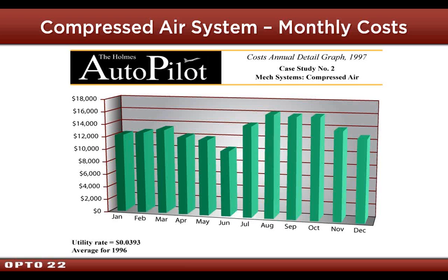He said, "By changing the way we were controlling our compressors, we've knocked 25% off of our daily and weekly consumption and cost, and it's going to save us $250,000 this year." This was a GE plant spending $1 million a month. They had 84 submeters they were reading by hand and putting in a spreadsheet. So they weren't managing it, they were reporting it. And these were people that were tracking pads of papers, and they didn't know where that $1 million a month went.